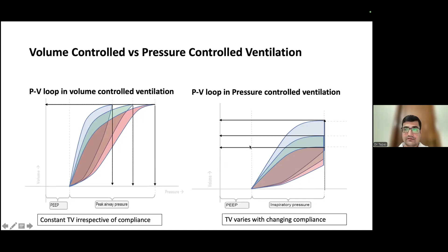Okay. So here the clinician who is operating the baby on pressure control ventilation has to manually reduce the pressure so that the tidal volume that is delivered post surfactant matches that of the physiological tidal volume. However, in case of volume control ventilation, the weaning of the pressure is automatic. Okay. So to conclude, in volume control ventilation, there's a constant tidal volume irrespective of the compliance, whereas in pressure control ventilation, the tidal volume varies with change in compliance, and hence one has to reduce the pressure post surfactant so that the tidal volume that is delivered to the lung matches that of the physiological needs.